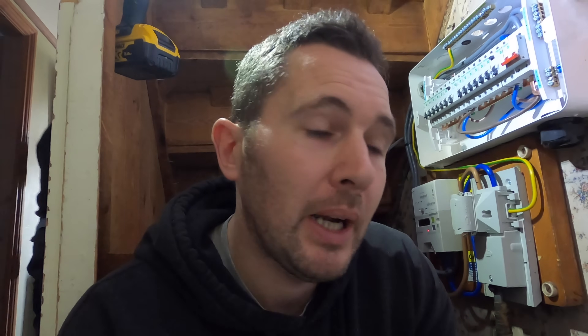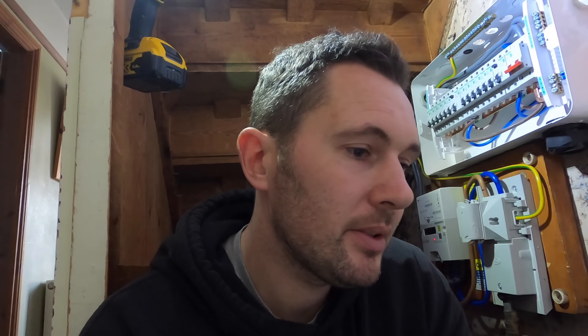Me and Lou are testing the house today. We're stupidly busy so we don't really need this job, to be honest. Believe it or not, the house is testing perfectly - nothing wrong with it overall. I've got no CPC continuity for the boiler, but apparently I do according to the sheet I've got in front of me. The kitchen was on a 16-amp radial. Let me take you into the downstairs loo.